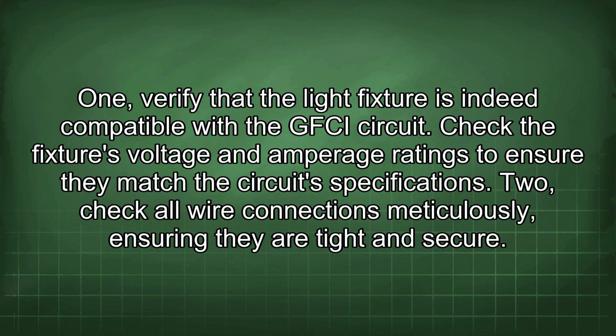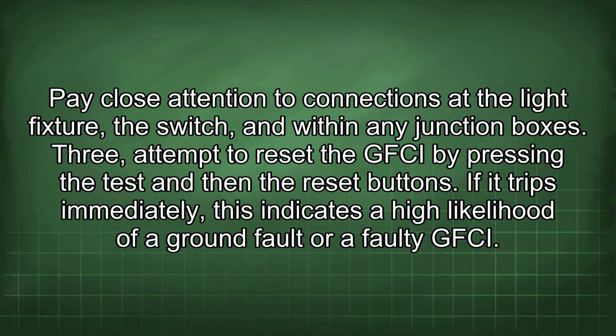1. Verify that the light fixture is indeed compatible with the GFCI circuit. Check the fixture's voltage and amperage ratings to ensure they match the circuit's specifications. 2. Check all wire connections meticulously, ensuring they are tight and secure. Pay close attention to connections at the light fixture, the switch, and within any junction boxes. 3. Attempt to reset the GFCI by pressing the test and then the reset buttons. If it trips immediately, this indicates a high likelihood of a ground fault or a faulty GFCI.